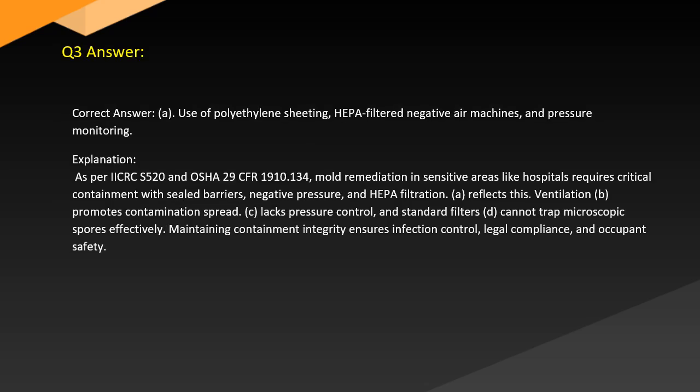Answer. Correct answer: A. Use of polyethylene sheeting, HEPA filtered negative air machines, and pressure monitoring. Explanation. As per OSHA 29 CFR 1910.134, mold remediation in sensitive areas like hospitals requires critical containment with sealed barriers, negative pressure, and HEPA filtration.